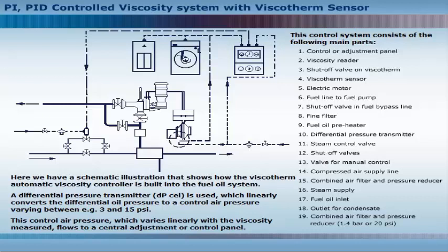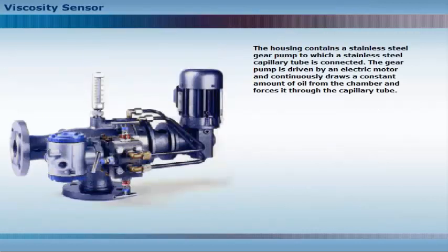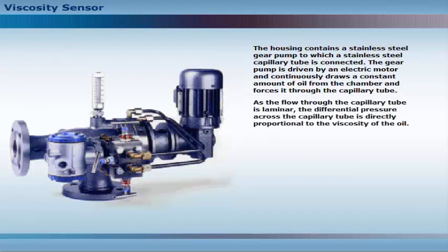Combined air filter and pressure reducer. The housing contains a stainless steel gear pump, to which a stainless steel capillary tube is connected. The gear pump is driven by an electric motor and continuously draws a constant amount of oil from the chamber and forces it through the capillary tube. As the flow through the capillary tube is laminar, the differential pressure across the capillary tube is directly proportional to the viscosity of the oil.